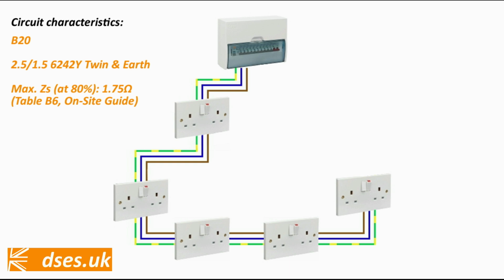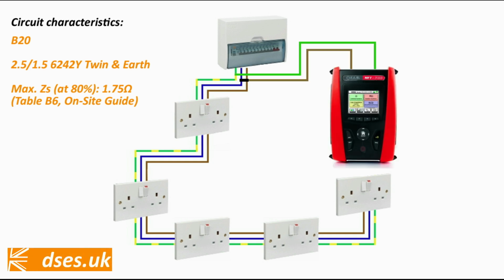As part of our inspection and testing procedure, there are 2 dead tests we already perform on this circuit as part of a competent EICR, which will help in checking for potential arc faults. Insulation resistance testing may pick up damaged insulation between cable cores or live parts to earth, and we're already used to performing IR testing to ensure RCDs won't be troubled.